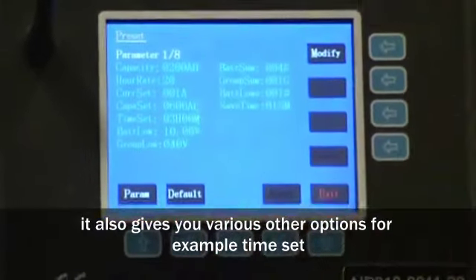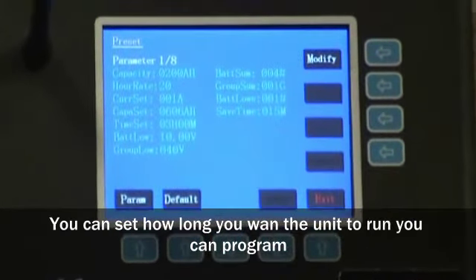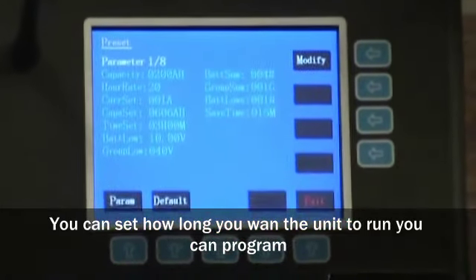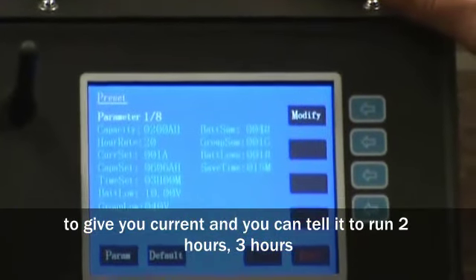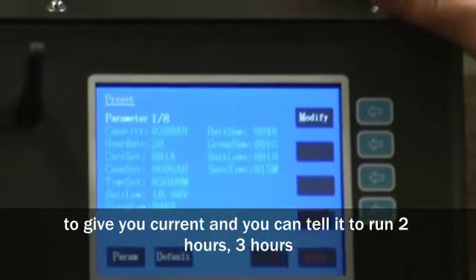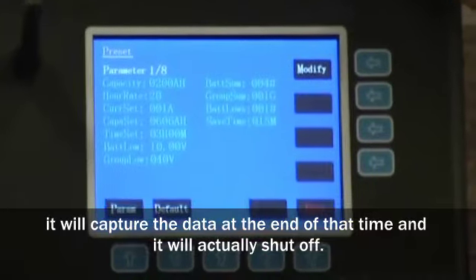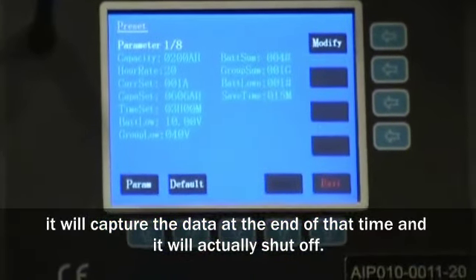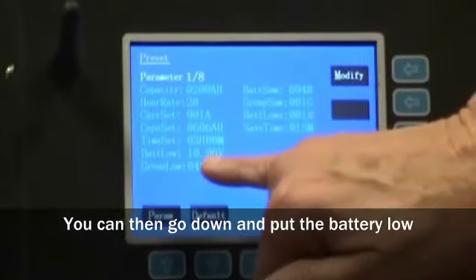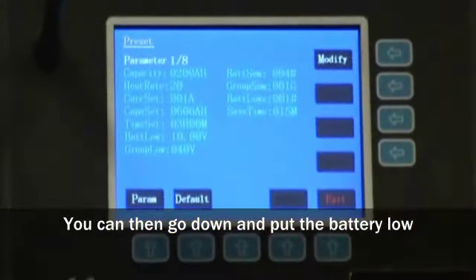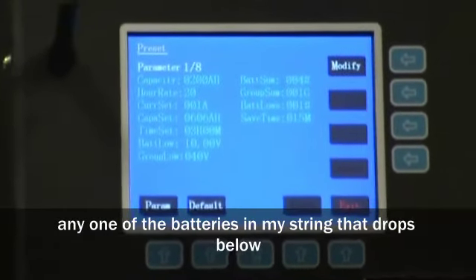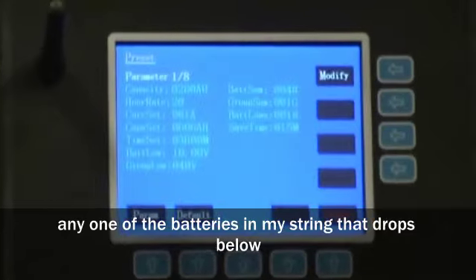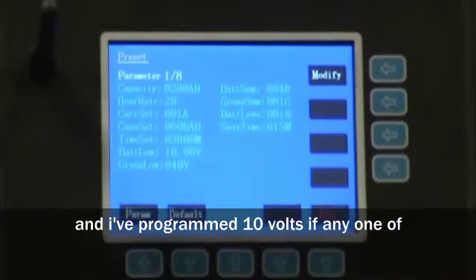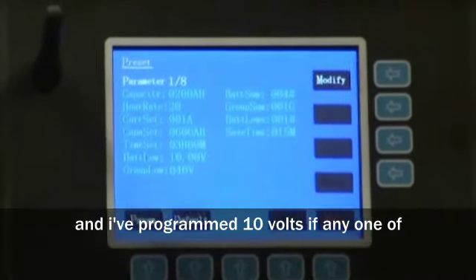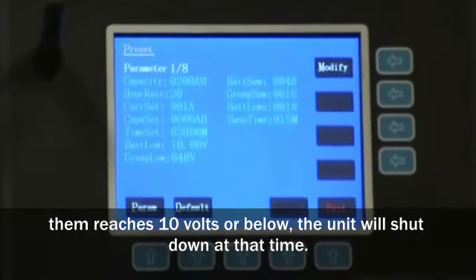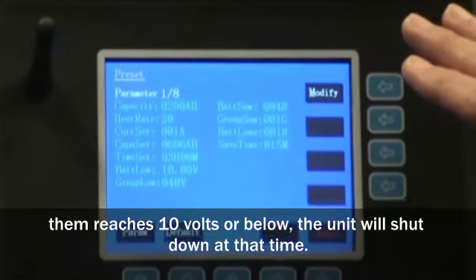For example, time set. You can set how long you want the unit to run. You can program a given current, and you can tell it to run 2 hours, 3 hours. It will capture the data. At the end of that time, it will actually shut off. You then can go down and put the battery low. Any one of the batteries in my string that drops below, and I've programmed in 10 volts. If any one of them reaches 10 volts or below, the unit will shut down at that time.